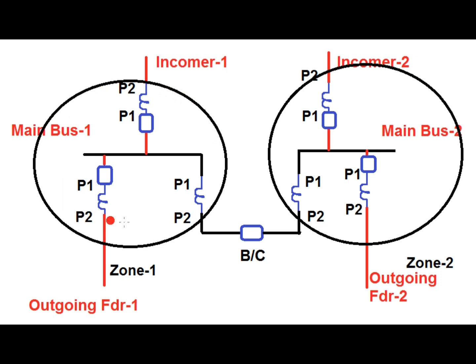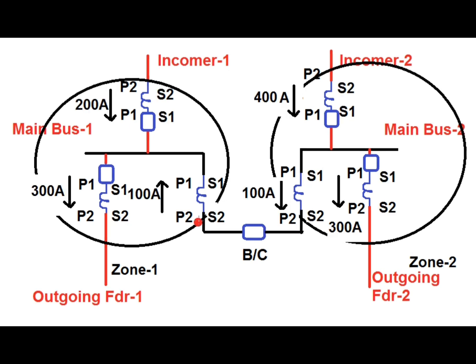There exist two zones: zone 1 or zone A covers the main bus 1 section, and zone 2 or zone B covers the main bus 2 section, each covering both ends of the bus coupler breaker. If a fault occurs at main bus 1, it is detected under zone 1 or zone A, which will trip all breakers connected to the main bus 1 section — including the bus coupler breaker — thereby isolating the faulty section.